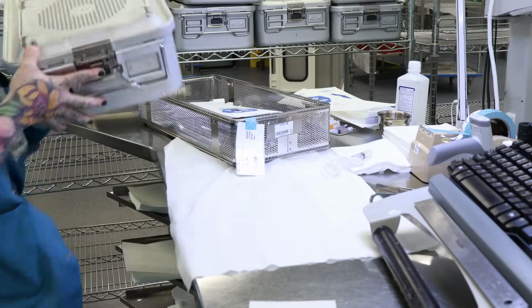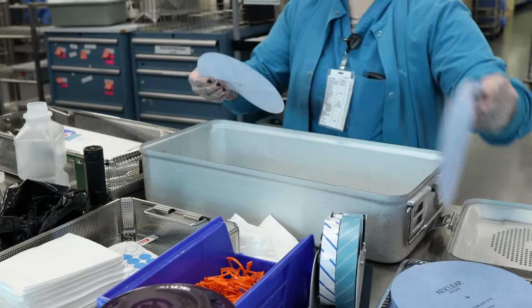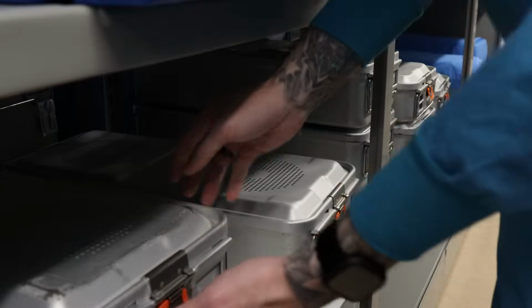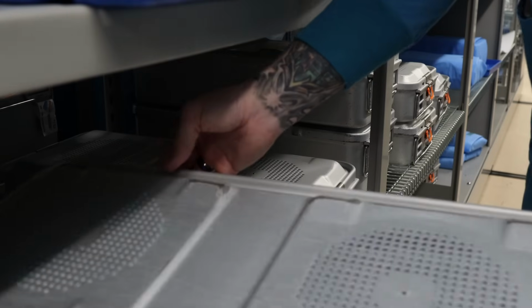There are several different options to package an instrument into an item that provides a barrier of protection for the instrument. Each one has 2 main jobs: to allow sterilant to penetrate and to reach the instruments during the sterilization process, and to protect the instruments after sterilization, making sure they remain sterile until they are opened in the operating room to be used. These different packaging items are containers, wraps, and peel pouches. Containers are generally made of metal and have disposable or reusable filters that prevent microorganisms from entering the tray, but allow the sterilant to penetrate. The containers also provide the greatest protection from damage or contamination after sterilization, since they have a pretty hard shell exterior. This hard exterior is more forgiving with transportation and other tray movements.